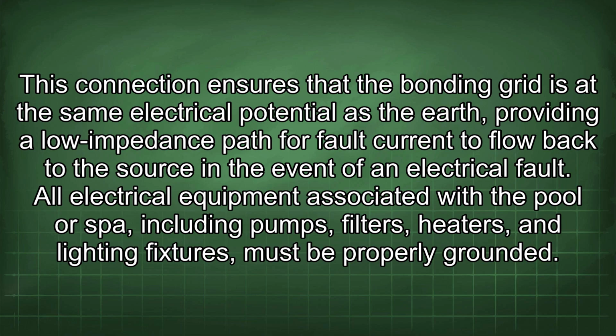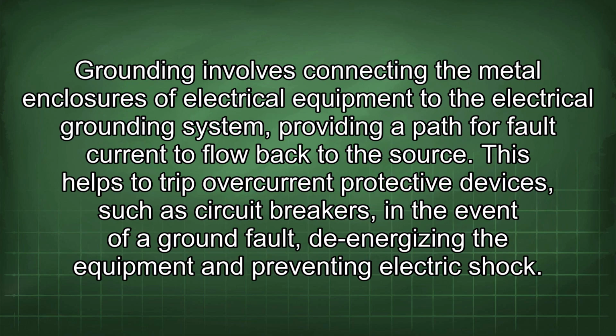All electrical equipment associated with the pool or spa, including pumps, filters, heaters, and lighting fixtures, must be properly grounded. Grounding involves connecting the metal enclosures of electrical equipment to the electrical grounding system, providing a path for fault current to flow back to the source. This helps to trip overcurrent protective devices, such as circuit breakers, in the event of a ground fault, de-energizing the equipment and preventing electric shock.